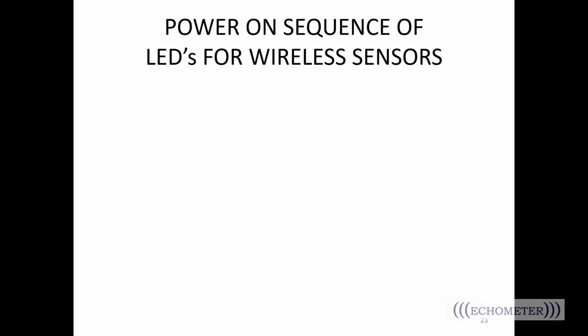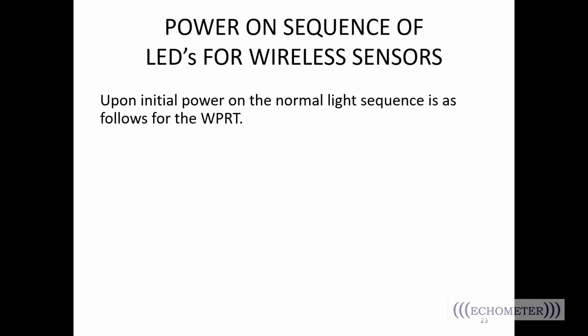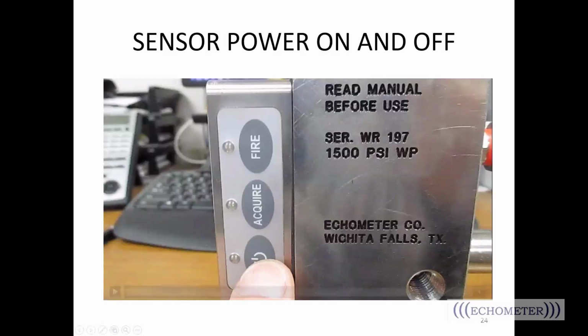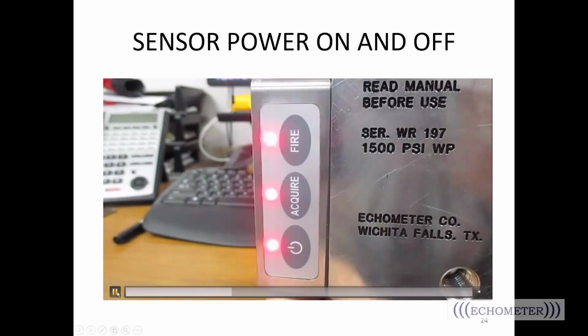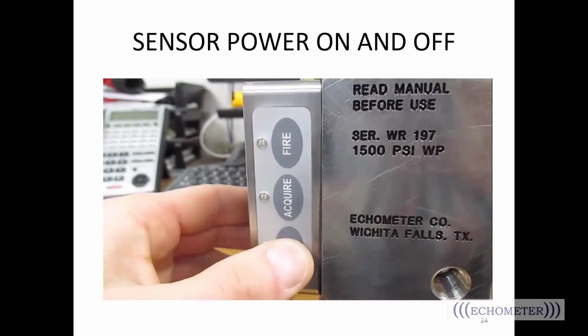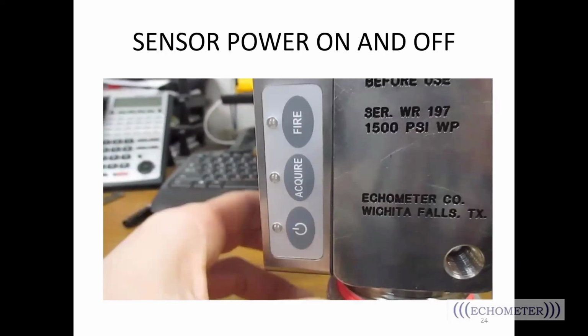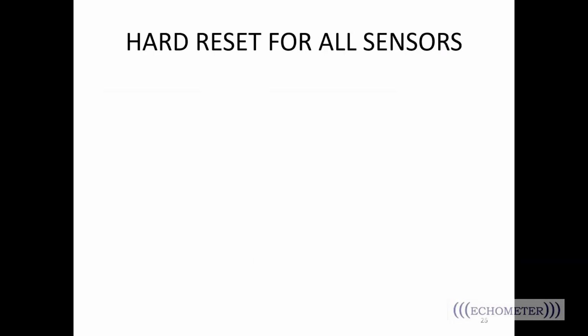So when you turn on your wireless sensors, there's a particular power on sequence that you'll see, and it's the same on the wireless guns and on the dynamometer sensors, on the pressure transducer as well. So this is an older membrane switch, but we're just looking at the behavior of the light. So when you turn it on, you'll press the power button, and you're going to see it flash green, flash red, and then the power button is going to flash really quickly one time for every 10% of power that you have remaining on that sensor. So if it flashes, I think here it flashed 3 times, that means you got 30% power, right? Or if it flashes 9 times, you've got 90% power remaining. So that's what it should do whenever you first power on the sensor.